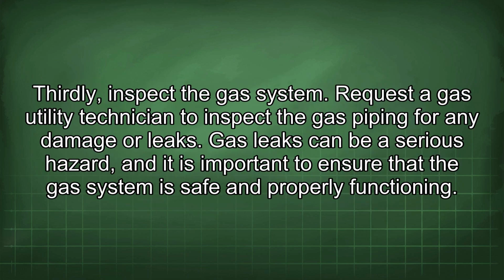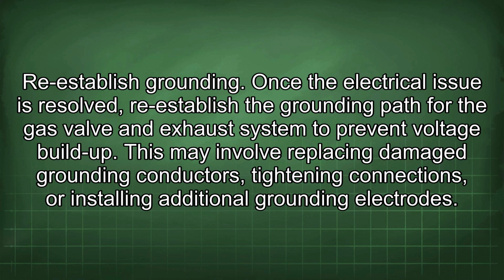Thirdly, inspect the gas system. Request a gas utility technician to inspect the gas piping for any damage or leaks. Gas leaks can be a serious hazard, and it is important to ensure that the gas system is safe and properly functioning. Re-establish grounding. Once the electrical issue is resolved, re-establish the grounding path for the gas valve and exhaust system to prevent voltage build-up. This may involve replacing damaged grounding conductors, tightening connections, or installing additional grounding electrodes.